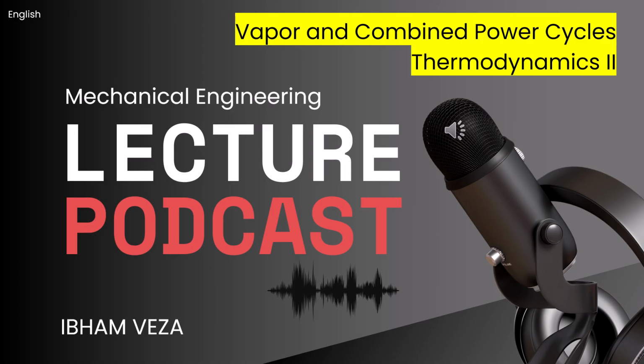Exactly. This allows them to vary the ratio of heat to power production. They might also have a valve to send high-pressure steam directly from the boiler to the process heater, bypassing the turbine entirely if maximum heat is needed. Or, if there's no process heat demand, they can run just like a regular power plant, sending all steam through the turbine to the condenser. So they're flexible. Very flexible.